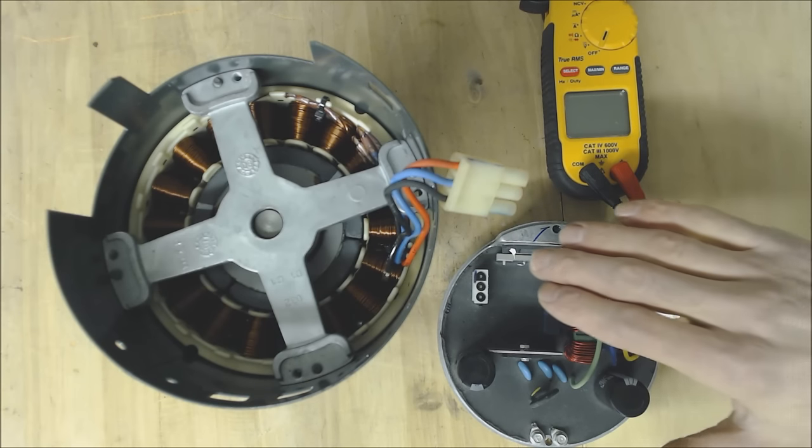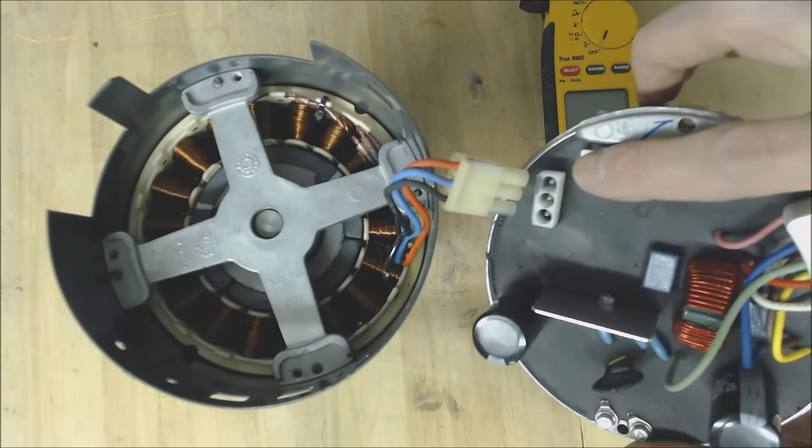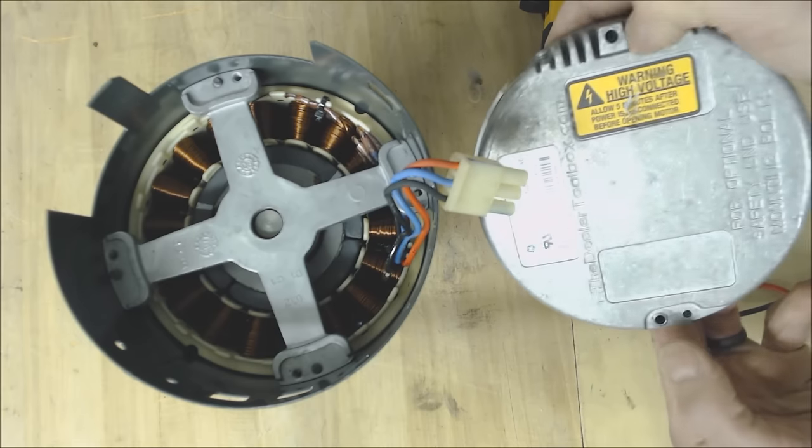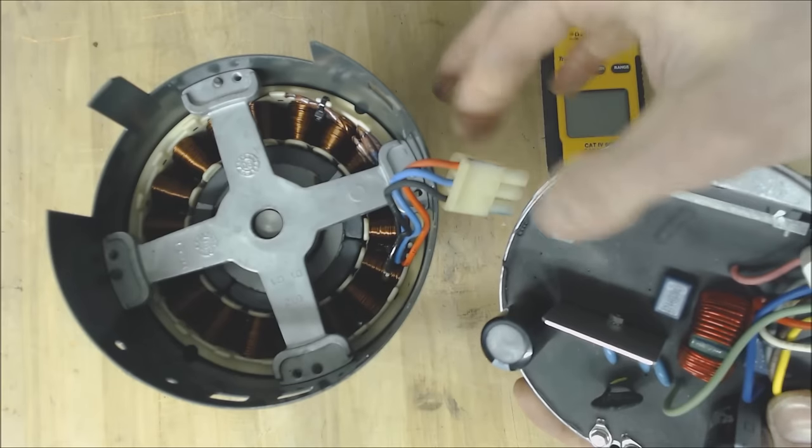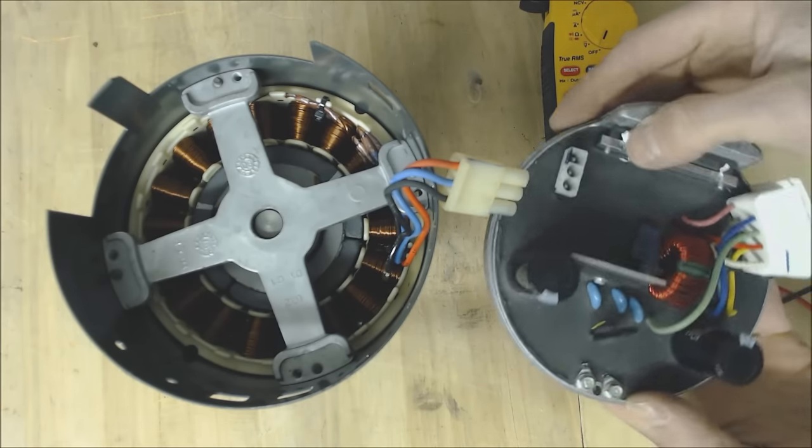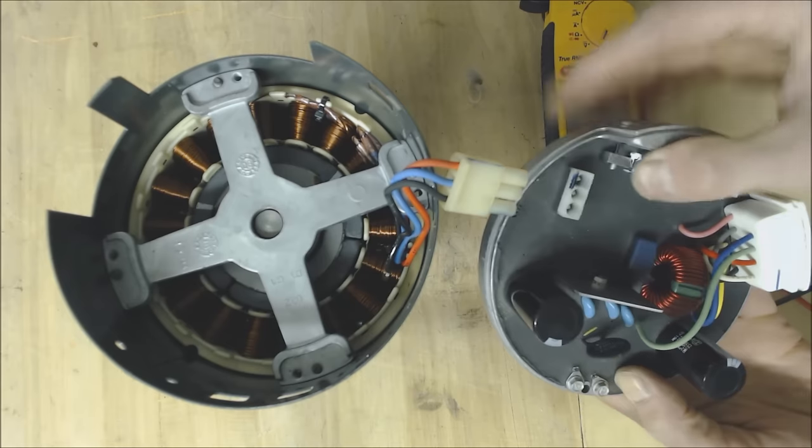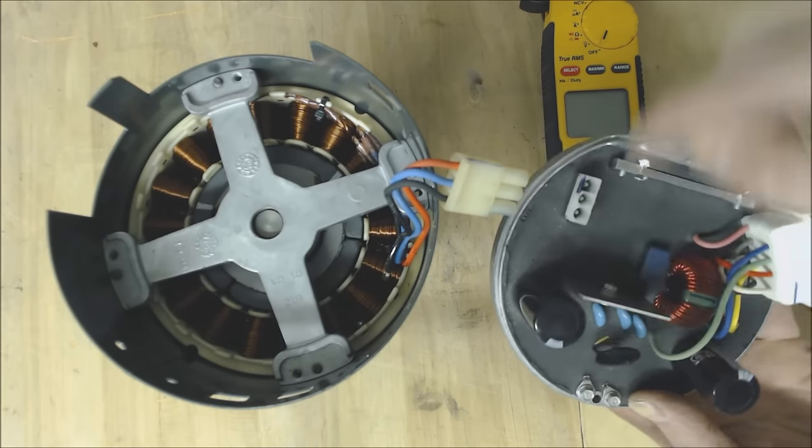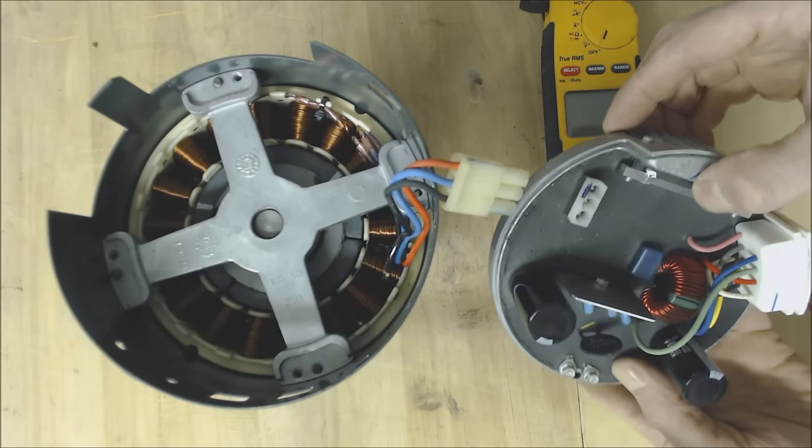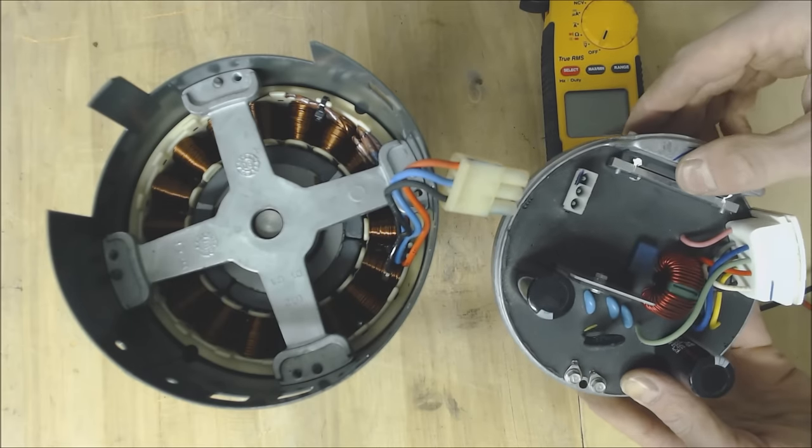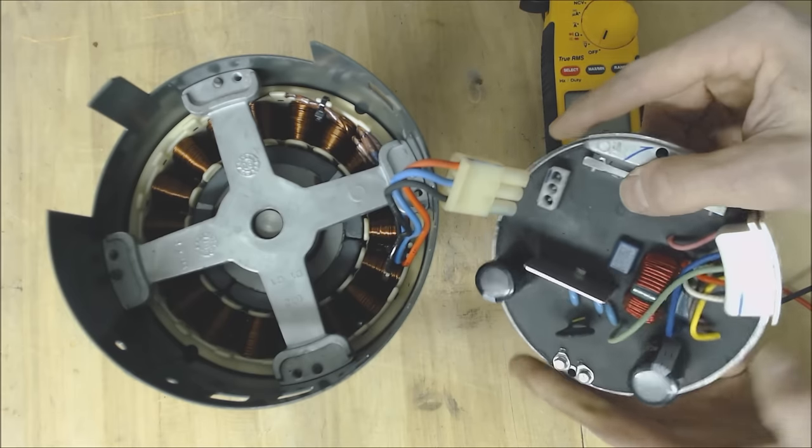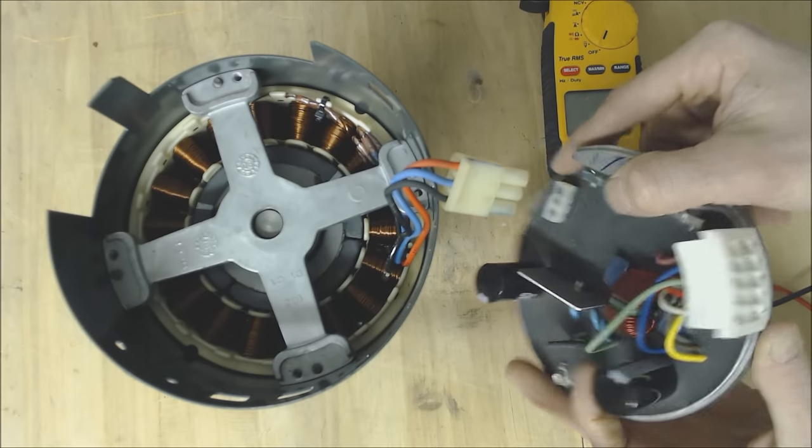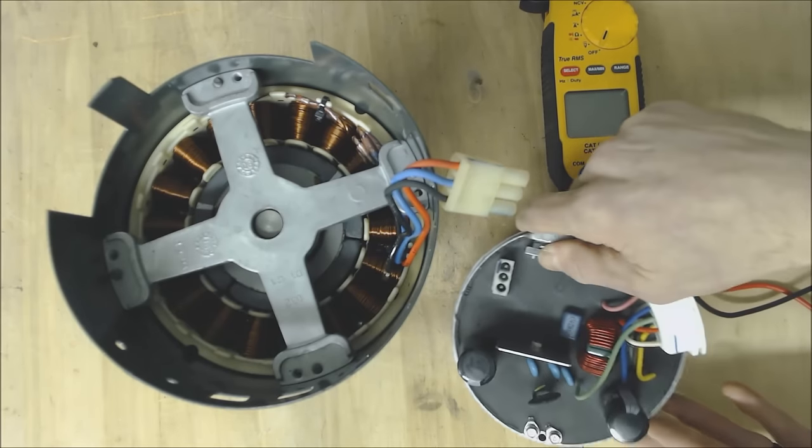So now that we have the motor apart you see that this connection all you have to do is when you unscrew these two screws right here you're just going to take it real easy and then just unclip this connector then you're going to visually inspect the module right here. So you make sure that there's no burn marks, the capacitors are in good shape. Typically it's one of these three items that are going to break on this unless you end up having accidental water damage come in here but this is all you're going to do on this is just a visual test.